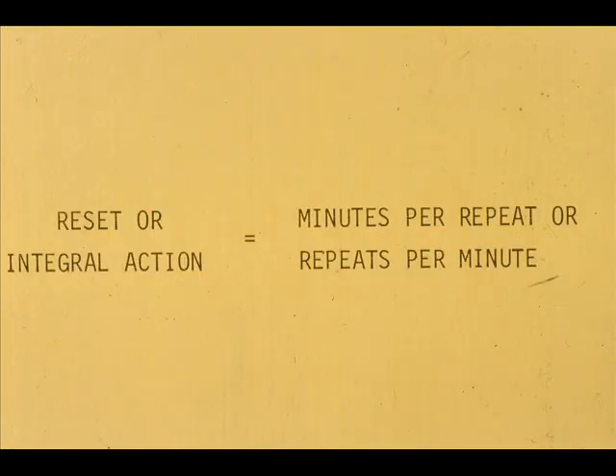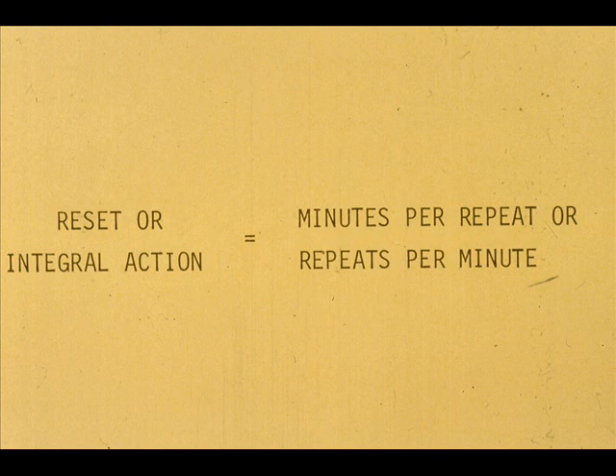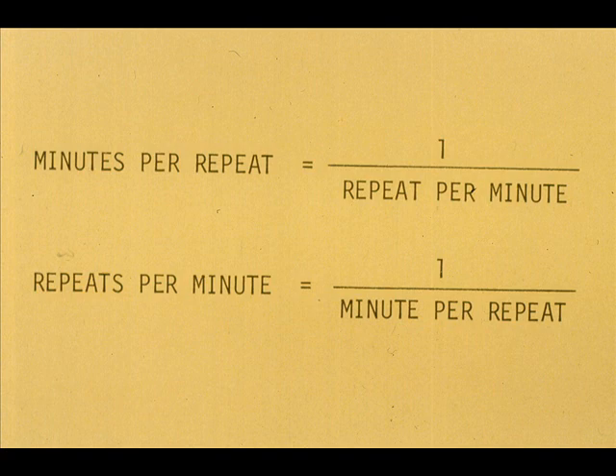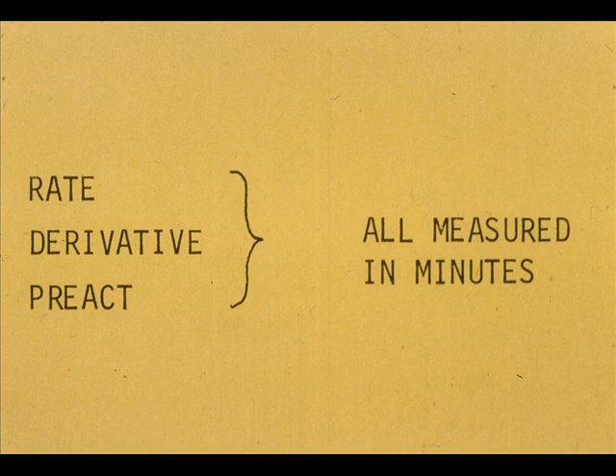Reset and integral action is measured in minutes per repeat or repeats per minute — one is the reciprocal of the other. Whether the term used is rate, derivative, or pre-act, the measurement is in minutes.